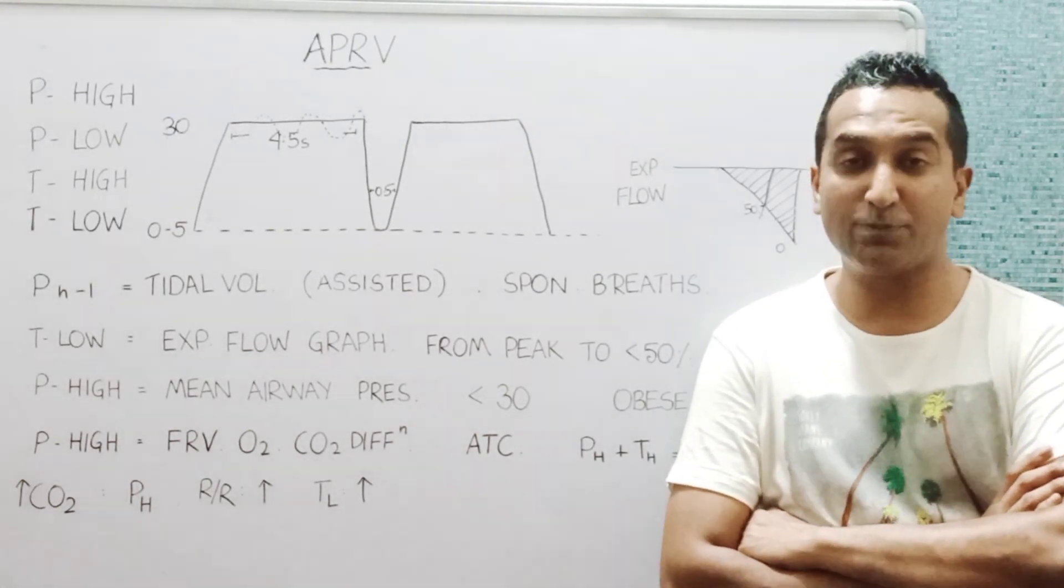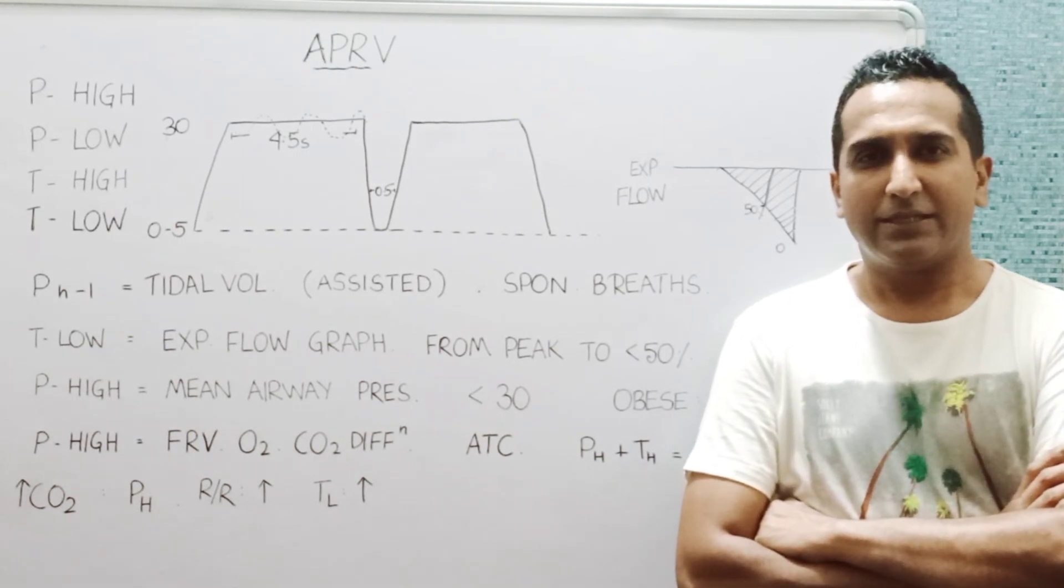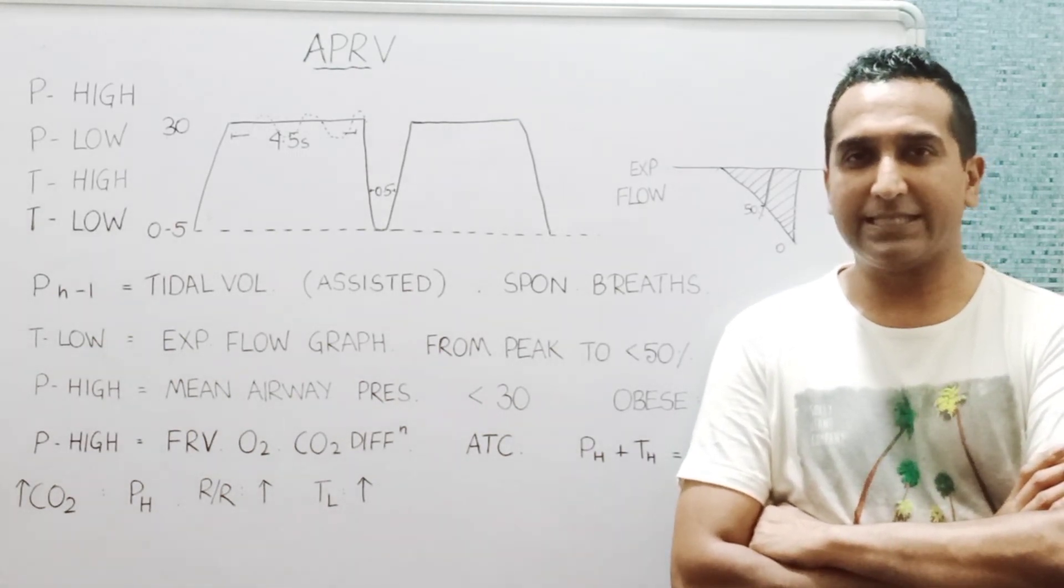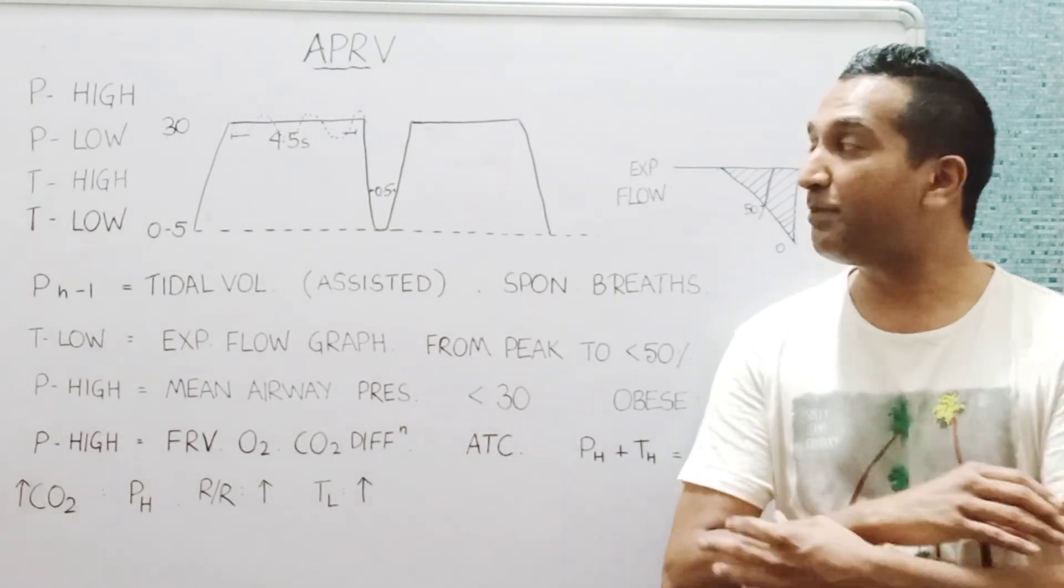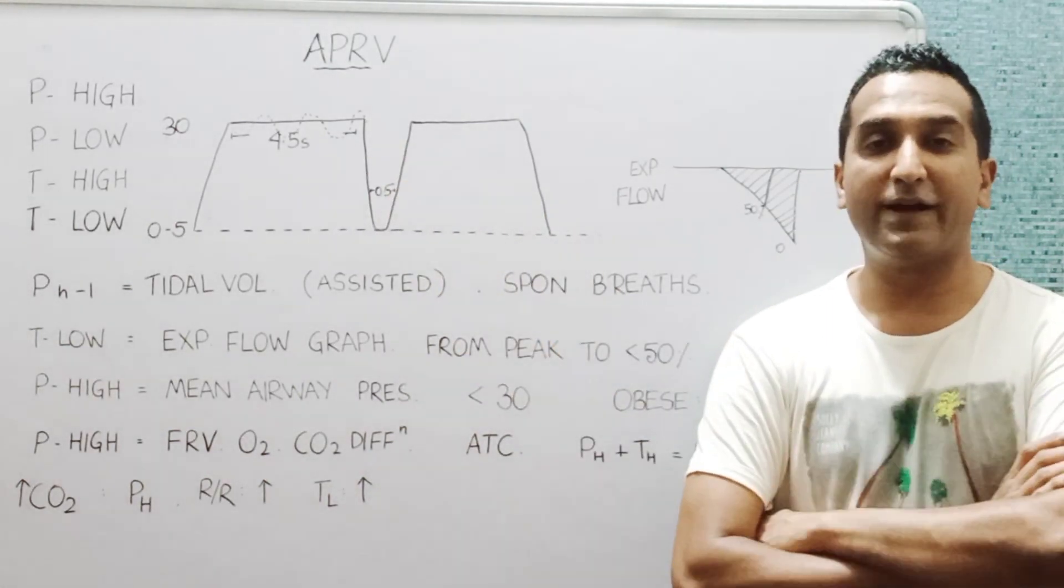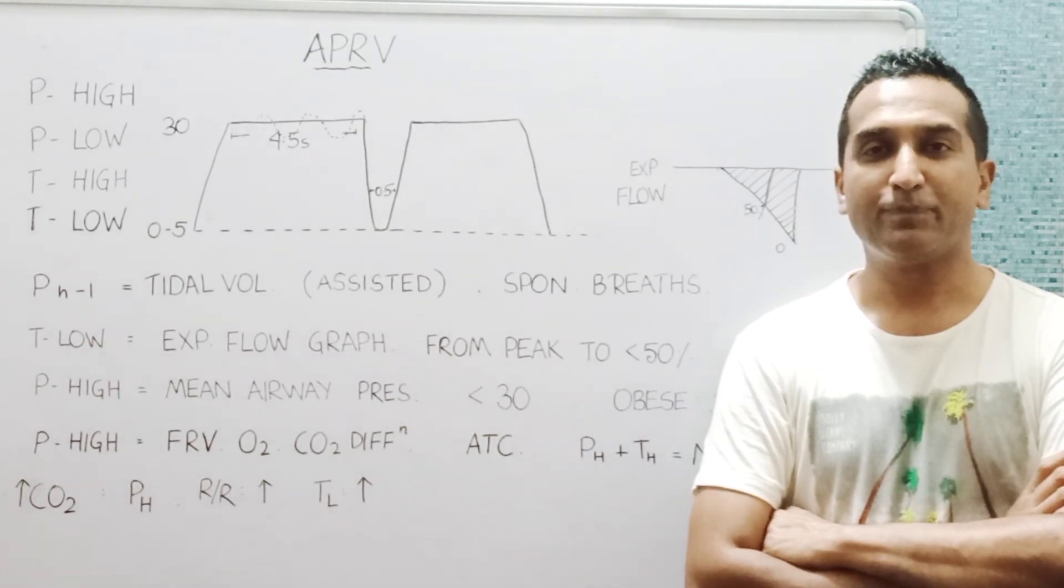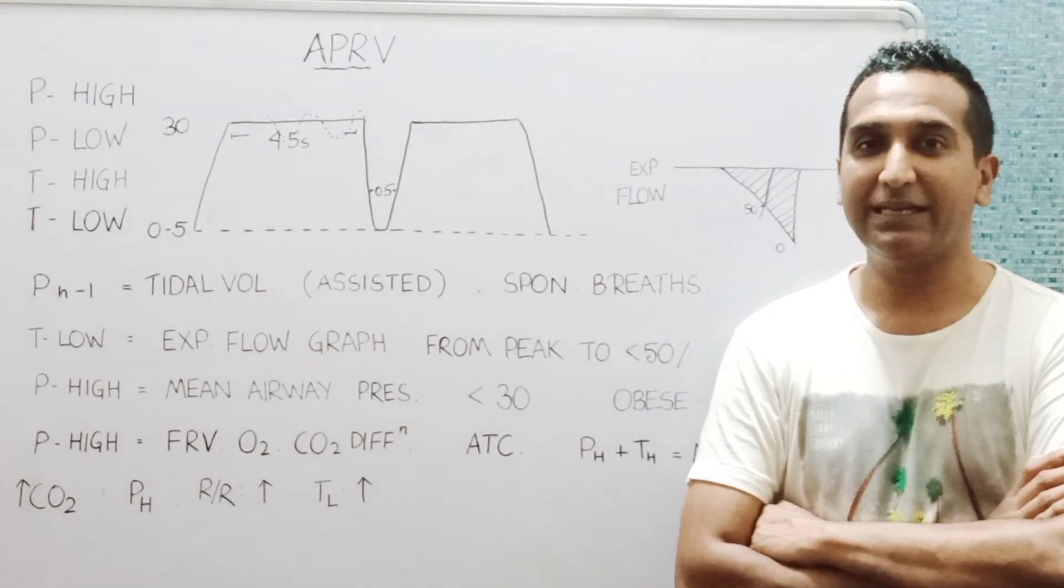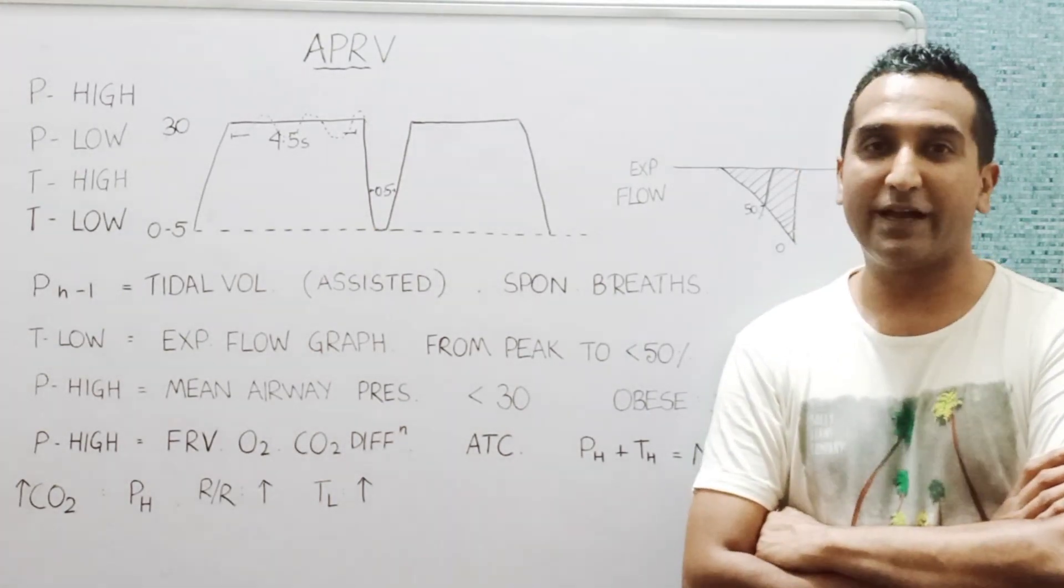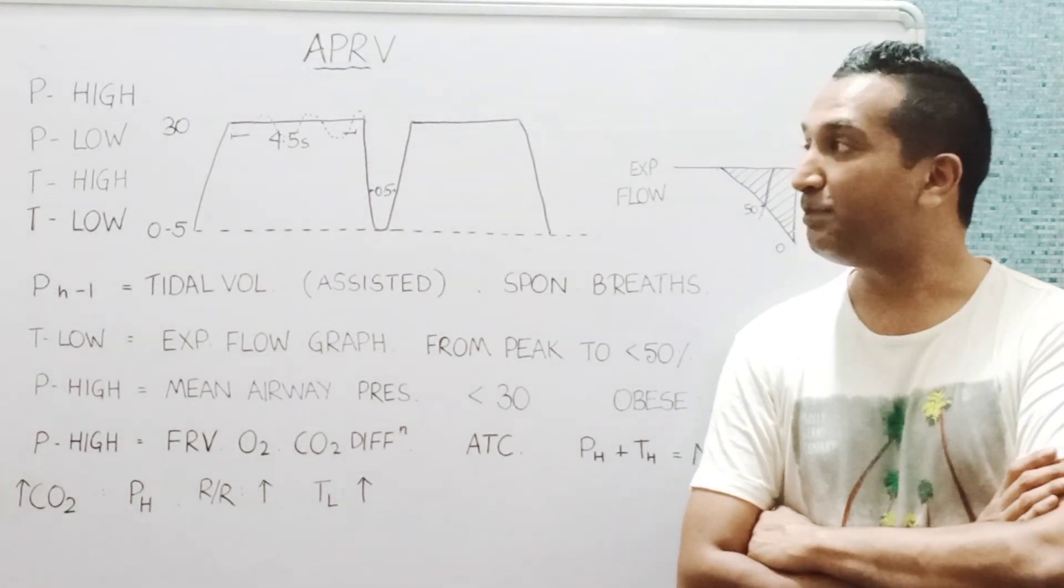With a rate of 12, let's say one cycle is of around 5 seconds. We will partition that 4.5 seconds for inspiration and 0.5 seconds for expiration, or 4.5 at P high and 0.5 at P low.